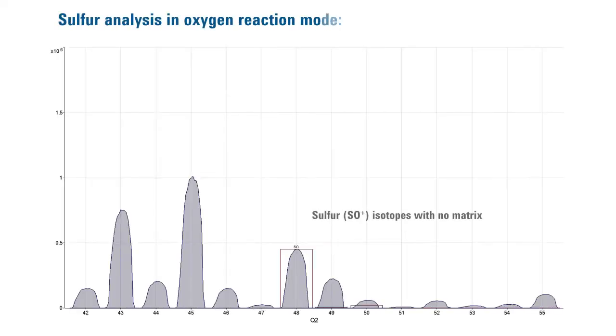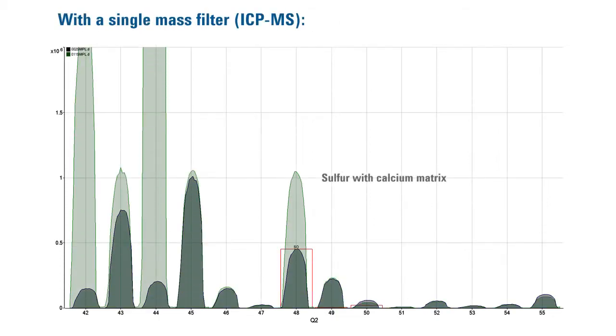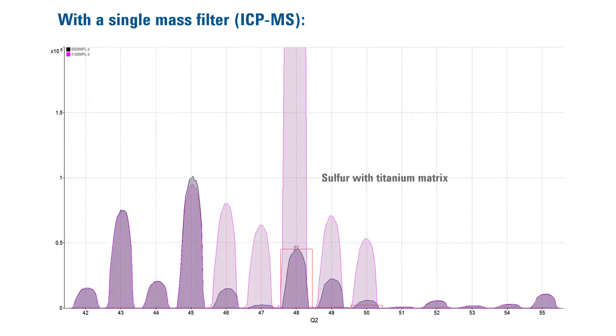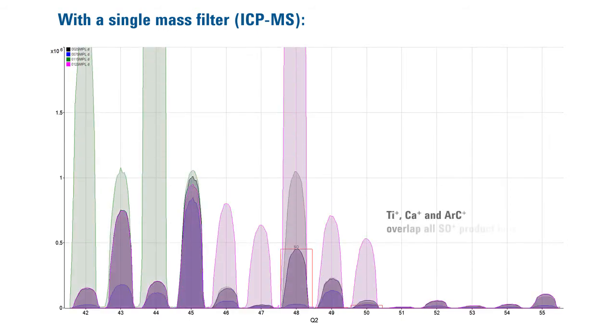For example, when sulfur is measured in oxygen reaction mode, the main isotope, sulfur-32, is measured as a sulfur oxide product ion at mass 48. But SO at mass 48 is overlapped by calcium-48, titanium-48, and an argon-carbon polyatomic ion, so the sulfur result is unreliable if any of these elements is present in the sample.